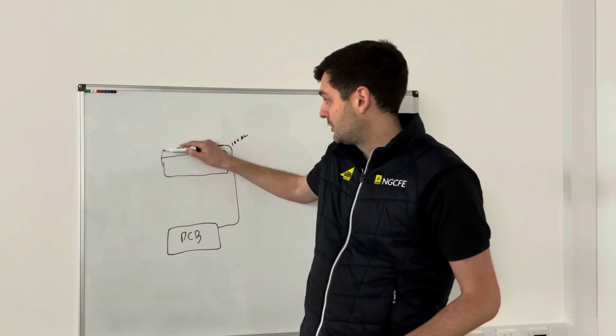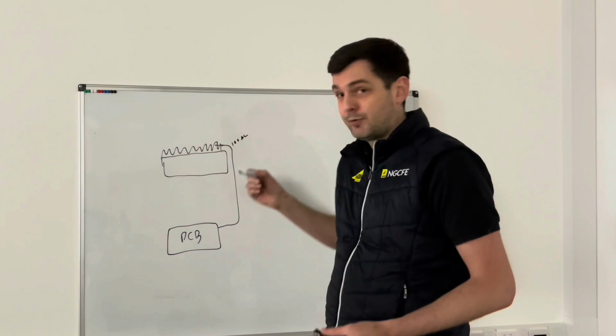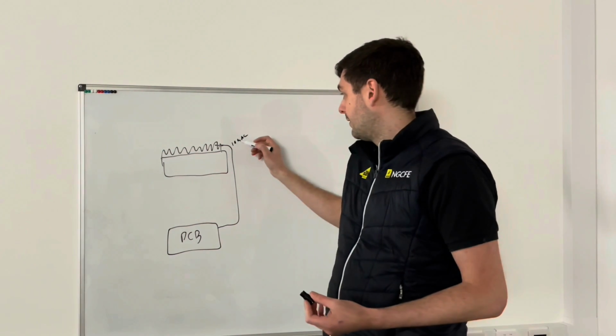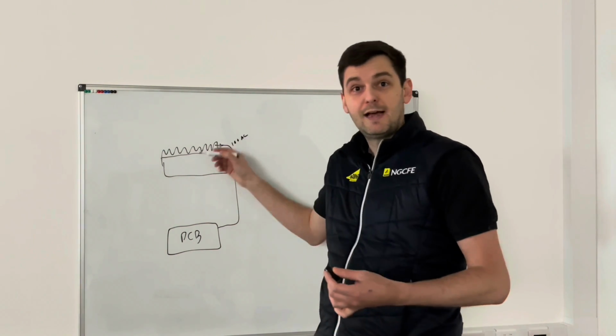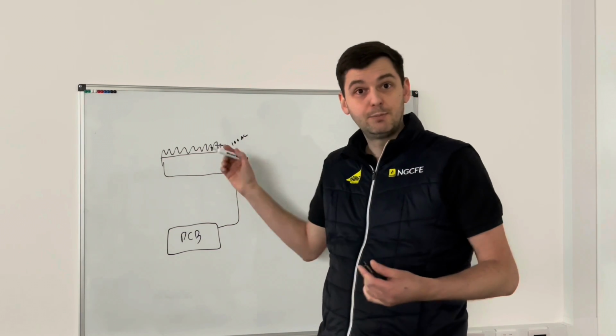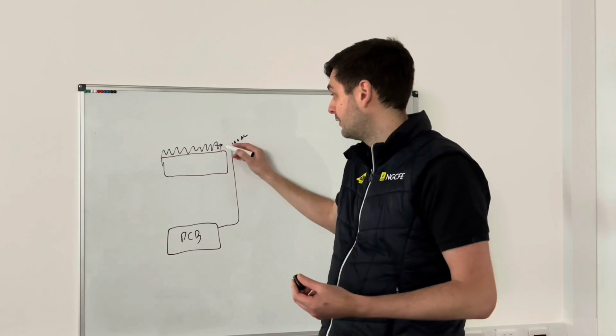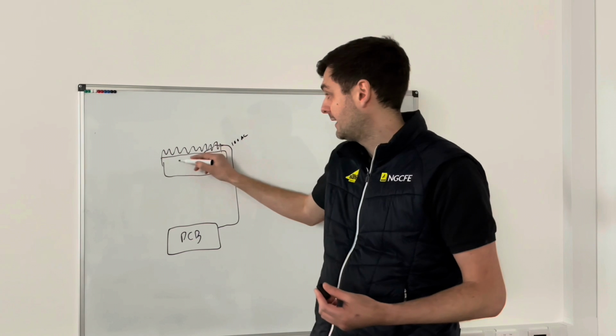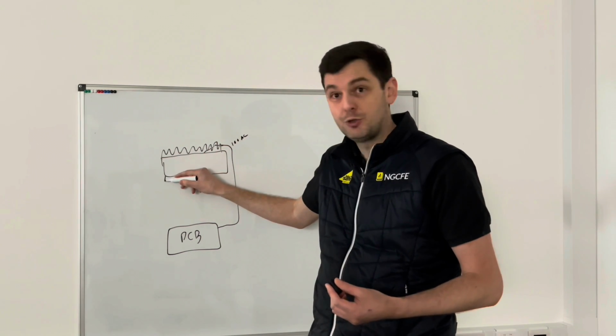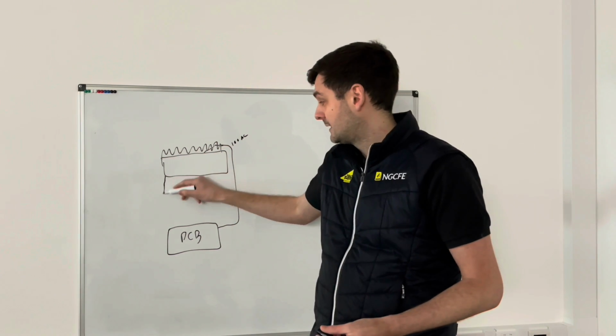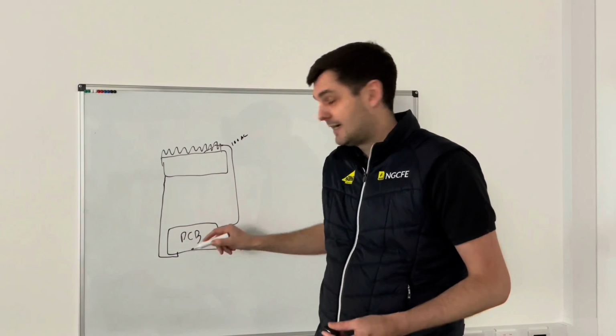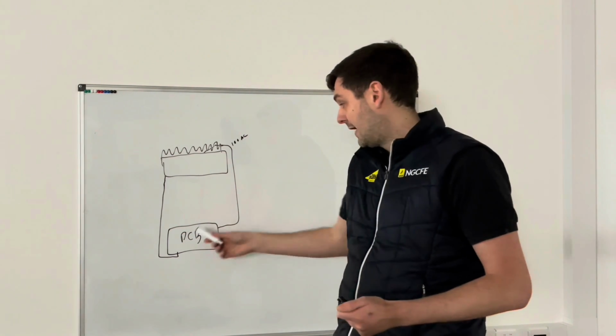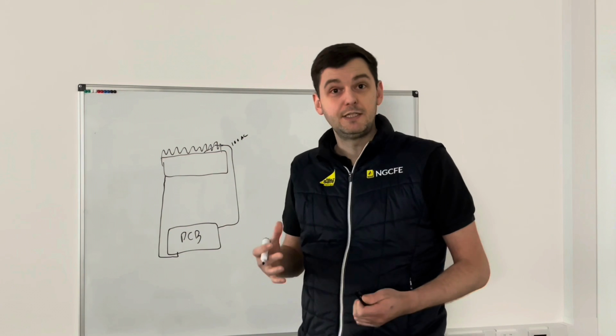When the flame establishes and engulfs the probe, that voltage rectifies through the flame and travels back to the board as DC current. So in travelling through the flame, it travels back via the earth lead usually, or a ground lead, back to the PCB as DC current. That board is always looking for DC current.